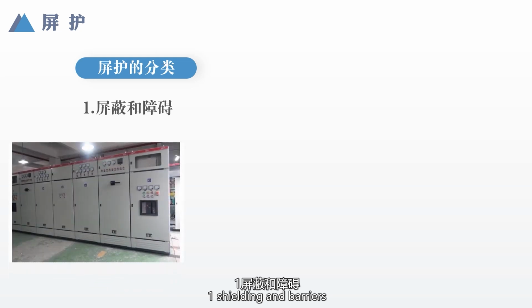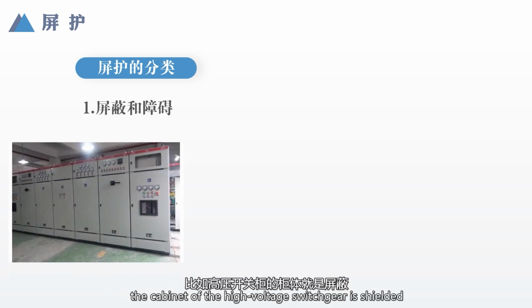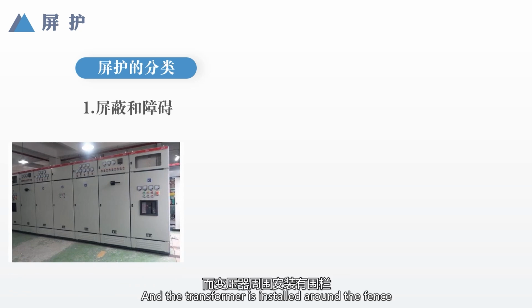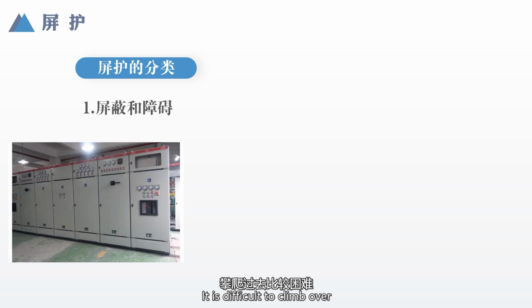Screen protection can be divided into 1. Shielding and barriers. For example, the cabinet of the high voltage switchgear is shielded, and the transformer is installed around the fence. It is difficult to climb over. This is the barrier.